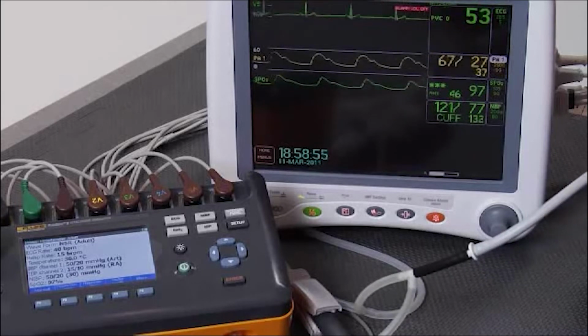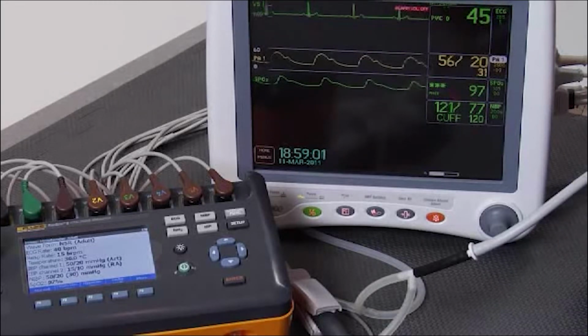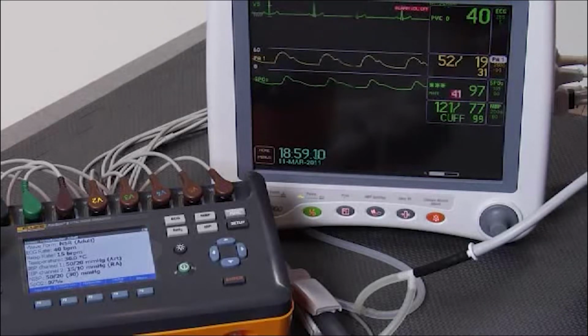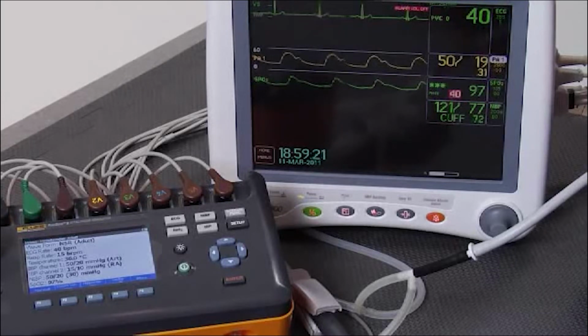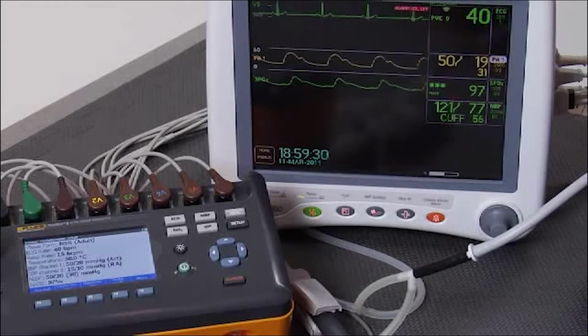We're looking for an ECG rate of 40 beats per minute, respiratory rate of 15 breaths per minute, and invasive blood pressure measurement of 50/20, and cuff blood pressure of 50/20 with a mean of 30, and an O2 sat of 97%. You can see that the ECG rate on the monitor is already 40. Our invasive blood pressure is 50/19, very close to 50/20. Our cuff is working on getting its measurement, and the O2 sat is 97, right on with what we asked for, what we're simulating.